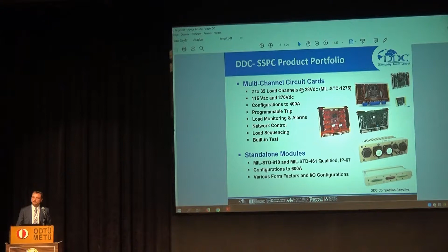As an overview of our card and module offering: it ranges from card products, from 1-channel, 2-channel cards, up to 32 independent channels on a single card. 115 volt AC, 270 volt DC cards, mainly 28 volt - most of our products are 28 volt - with configurations up to 400 amp controlled on a single card. These are mainly used in primary power distribution, for example for a turret application which needs a lot of power and current flow. We can control this with one of our SSPC cards.